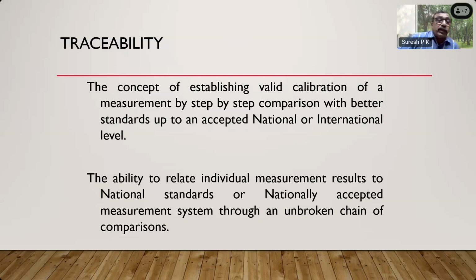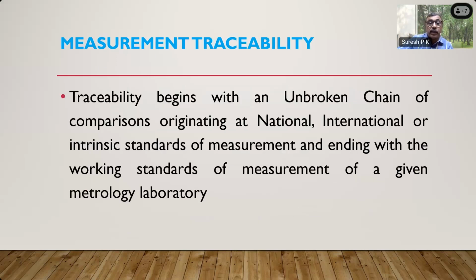Unbroken chain means then all your calibrations are valid. I'll come to that unbroken chain later. The concept of establishing a valid calibration of the measurement by step-by-step comparison with better standards. Traceability begins with the national or international intrinsic standard of measurement and ends with the working standards of measurement of a given metrology laboratory.